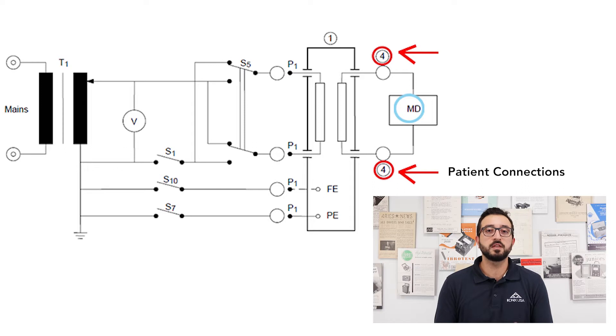In the second example, we will take a look at how leakage current can be measured between two patient leads or patient connections, or in other words, patient auxiliary current. In this case, the measuring device circuit is placed between two different patient connections to ensure that it measures the current that can flow between these two patient connections. Once again, we will simulate this under the fault conditions that we talked about, and the device shall be powered on at 110% of the rated voltage.